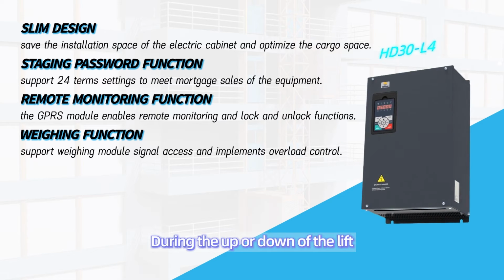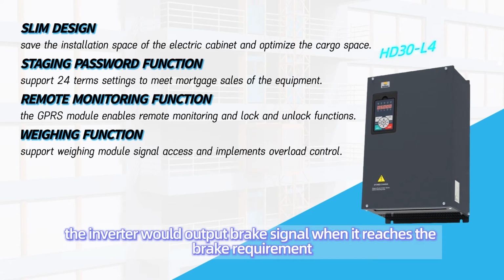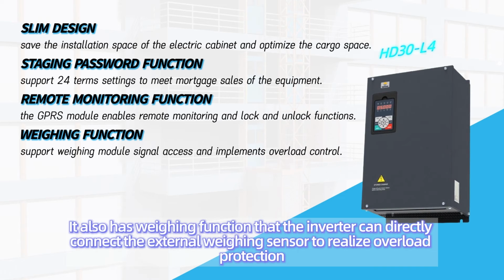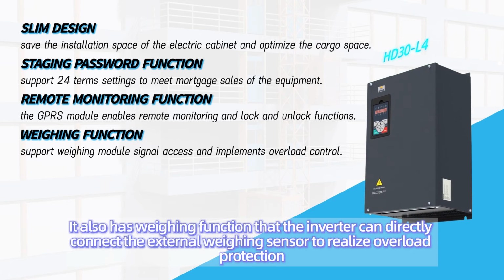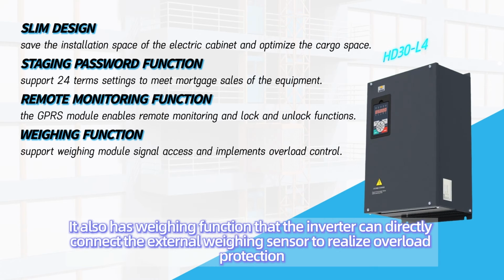During the up or down of the lift, the inverter will output a brake signal when it reaches the brake requirement, realizing the protection function. It also has a weighing function, so the inverter can directly connect to an external weighing sensor to realize overload protection.